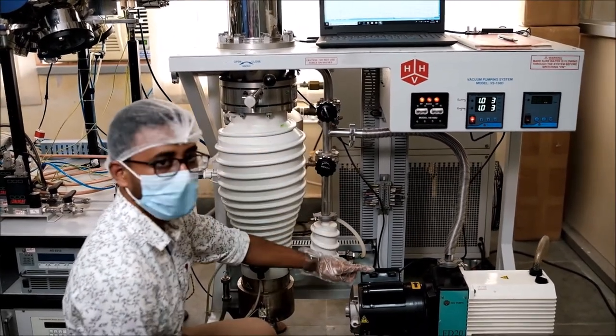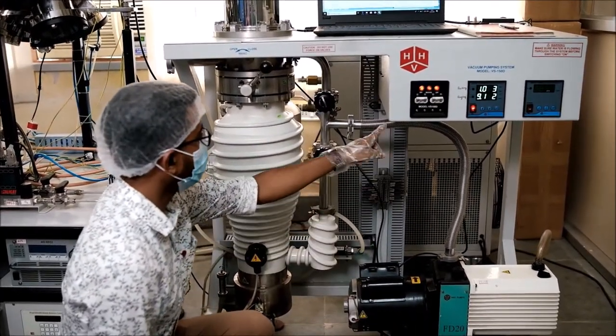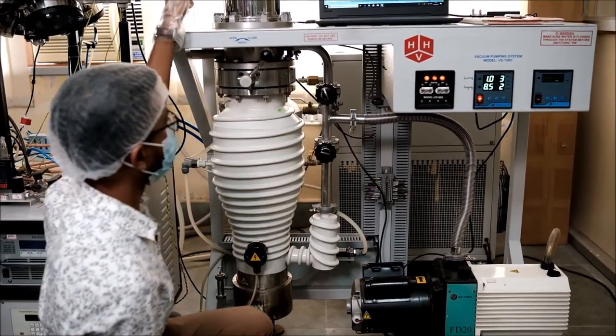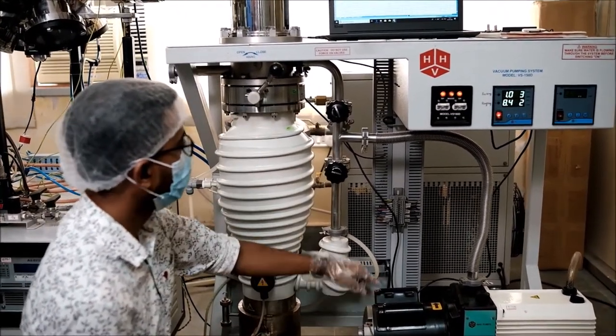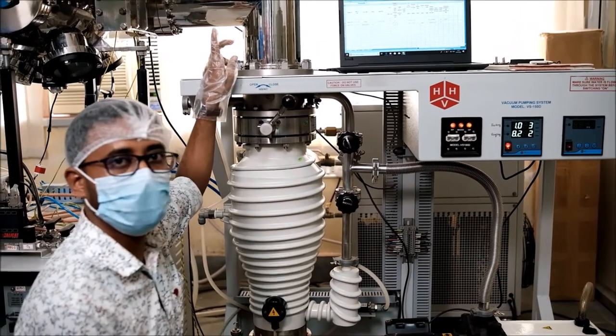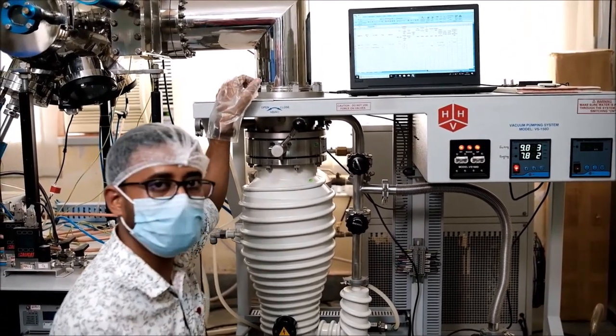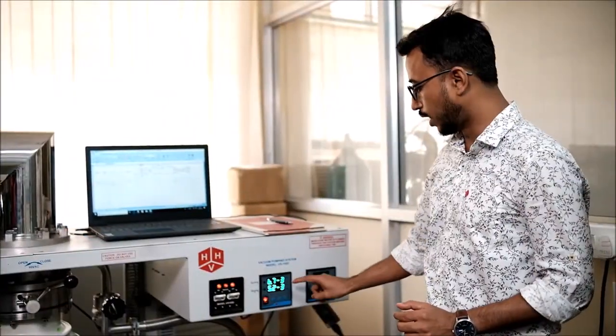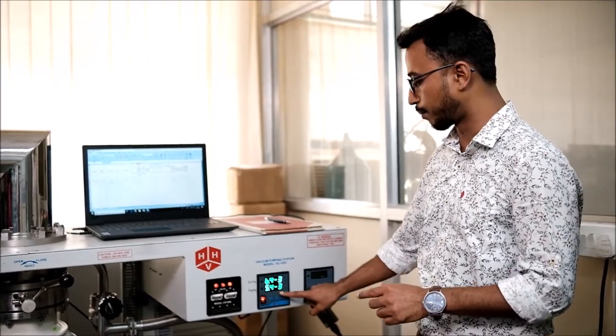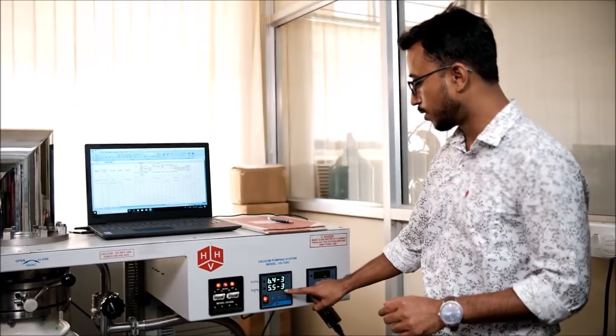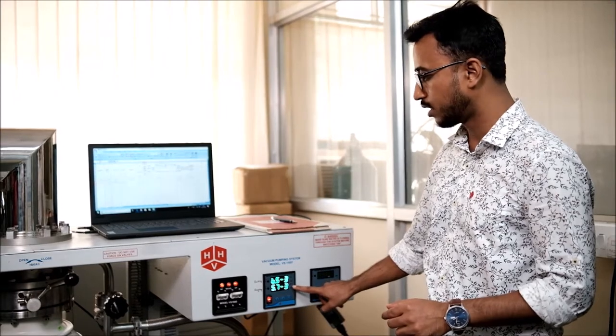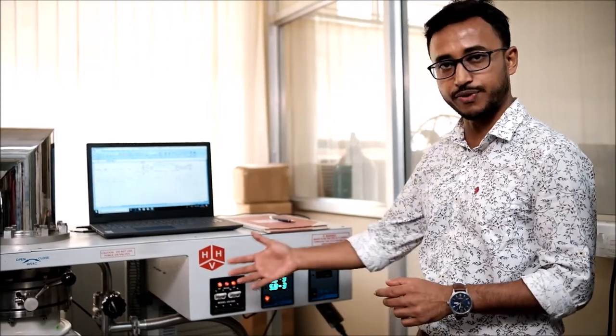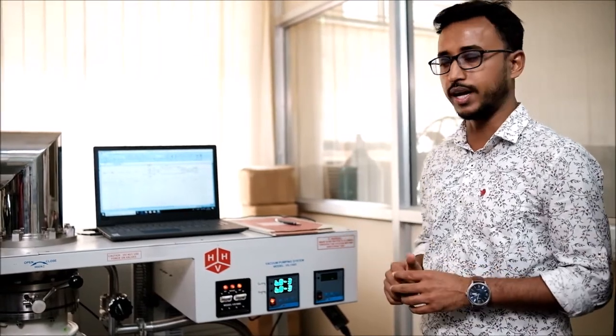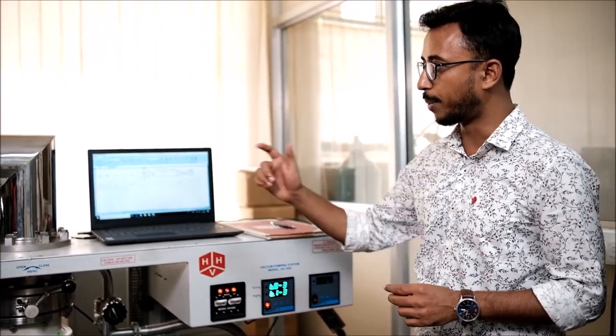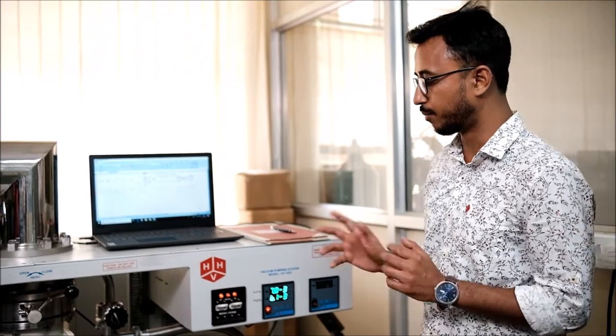So now this rotary pump is connected through this valve to the chamber. So now it will evacuate till 10^-3 millibar of pressure. So we wait by then. So now the roughing pressure, that means the chamber pressure, has reached 10^-3 millibar of pressure, and also we have passed enough time to heat up the diffusion pump oil. So now we are ready to open the chamber for high vacuum pump.